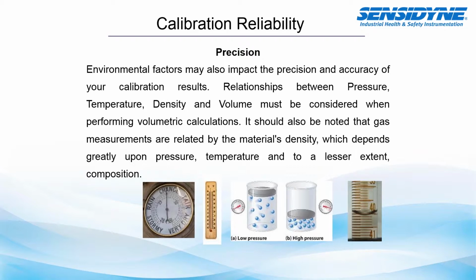Environmental factors may also impact the precision and accuracy of your calibration results. It's important to understand the relationship between pressure, temperature, density, and volume when performing volumetric calculations. It should also be noted that gas measurements are related by the material's density, which depends greatly upon pressure, temperature, and to a lesser extent, the composition of the air that is being passed through the calibrator.